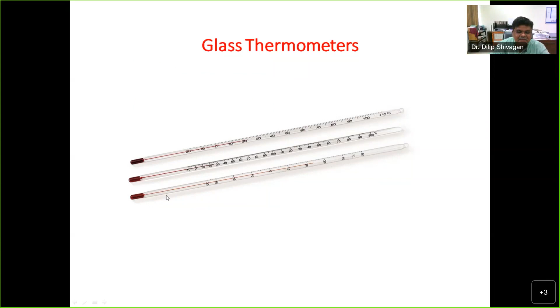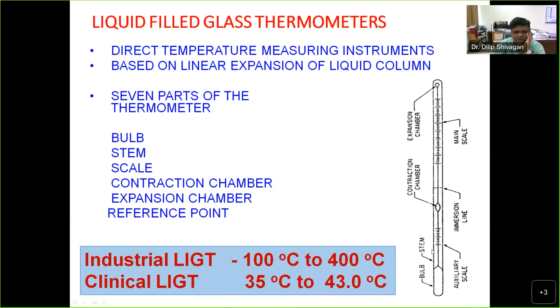So if you exceed the temperature, suppose you are measuring 200 and unfortunately you exceed it, then this mercury will come and stay here. So it is the volume expansion. Okay, and the linearity of the measurement will depend on the linearity of this capillary. So this may vary depending on the temperature. So whenever you are measuring with a total immersion thermometer, you should always measure in a total immersion condition.